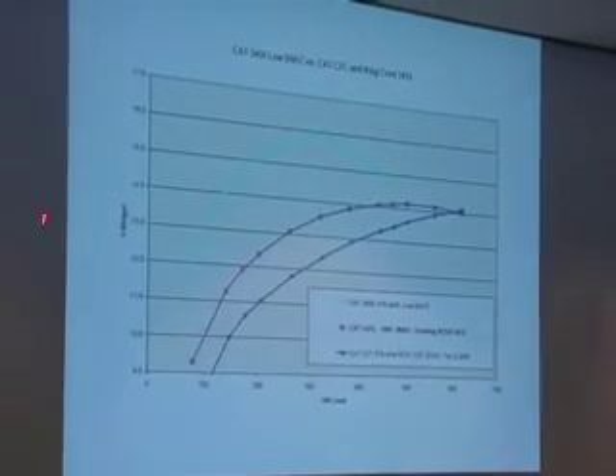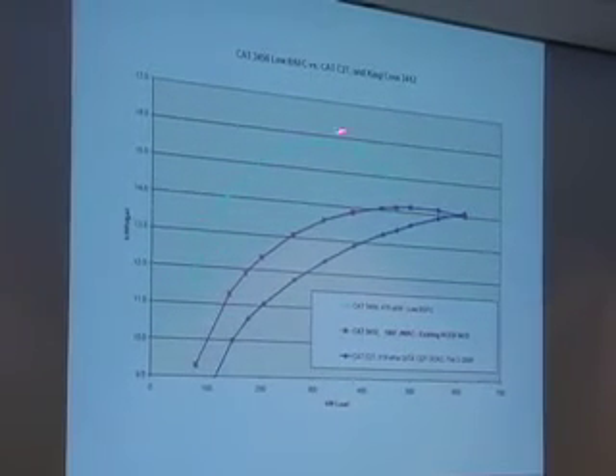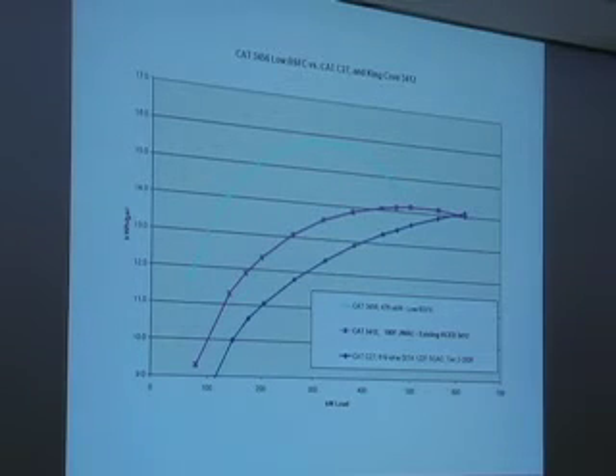Can you see that light blue curve there? That's the 3456 as well. I put this one up because one of the Alaskan utilities was looking at replacing a genset, and they thought seriously about installing this one, the Cat C27. You can see it's got somewhat similar range to the 3456, but look at that difference in efficiency—through its expected operating range, the difference is between 10 and 30% in efficiency.